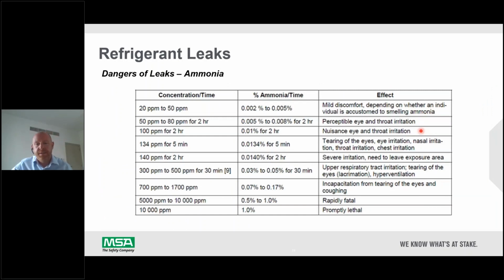Ammonia, of course, is used in lots of other industries, so there are lots of studies done on the risks of ammonia. You can see here, above 20 ppm starts to get mild discomfort, and then large leaks of an evaporator, a big leak up to 300 ppm, start to have damage on the respiratory system. So it's very important these are detected very early if these are used in a large food processing area, for example.